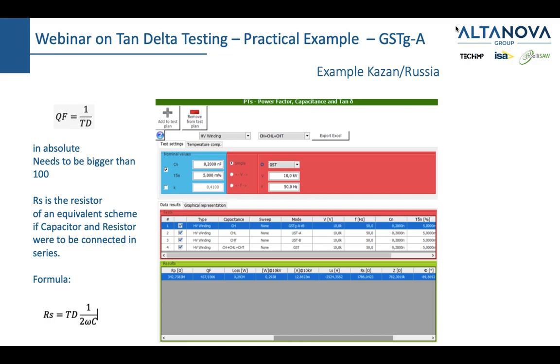Could you please explain length dependency on tan delta on a high voltage power cable? I think we just covered that, but in short, it depends very much on your capacitance per kilometer. If I can measure, let's say, 100 nanofarad with 12 kilovolts, and you have a capacitance of 100 nanofarad per kilometer, you could measure 1 kilometer. So feel free to send me a mail, and if you have some cables and you know their capacitances, we would be able to give you a more accurate reply.